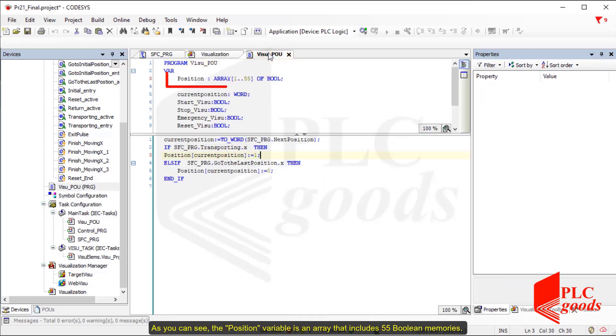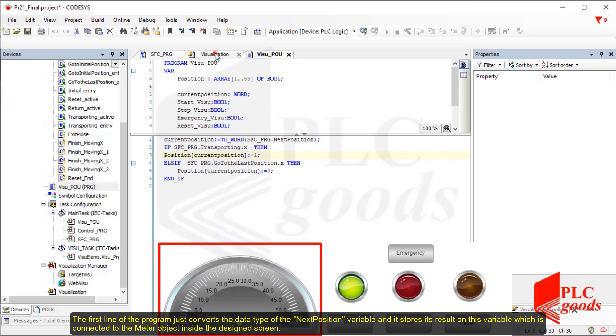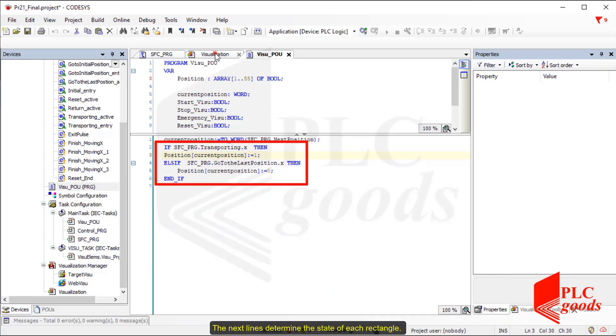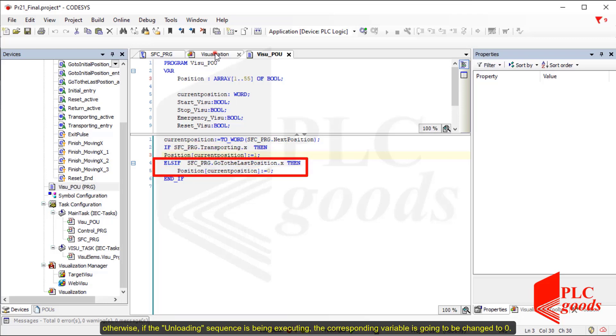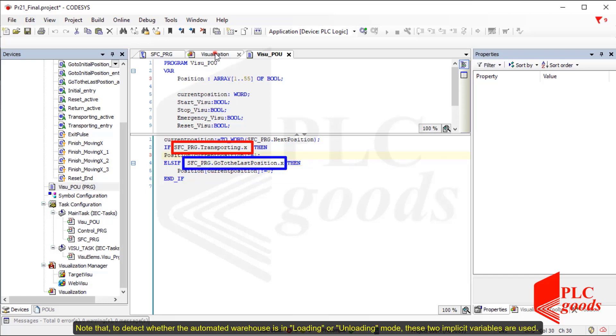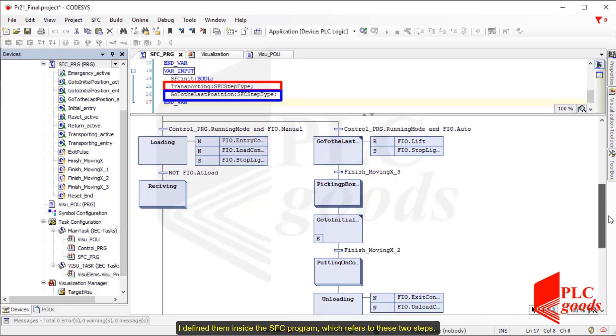As you can see, the position variable is an array that includes 55 Boolean memories. The first line of the program converts the data type of the next position variable and stores its result on a variable which is connected to the meter object inside the designed screen. The next lines determine the state of each rectangle. If the automated warehouse is in loading mode, the Boolean variable related to the current position is set to 1. Otherwise, if the unloading sequence is being executed, the corresponding variable is changed to 0. To detect whether the warehouse is in loading or unloading mode, two implicit variables are used, defined inside the SFC program which refers to these two steps.